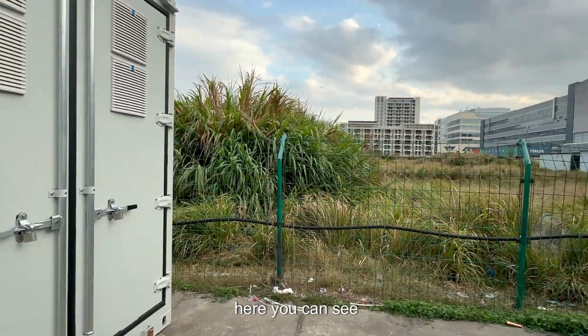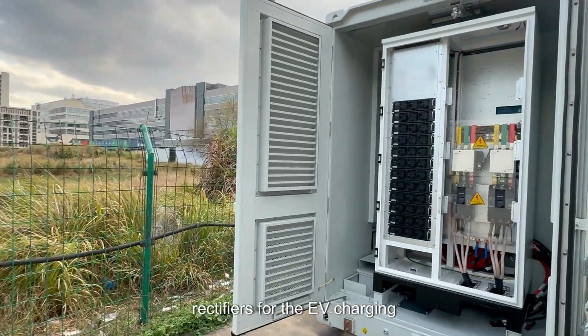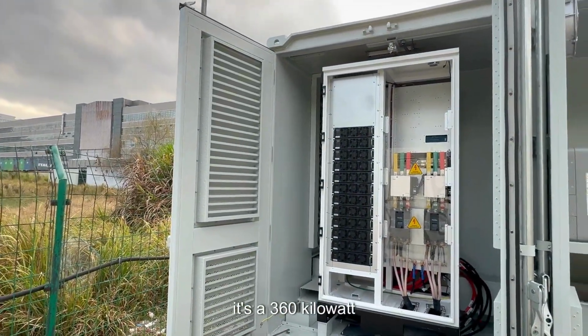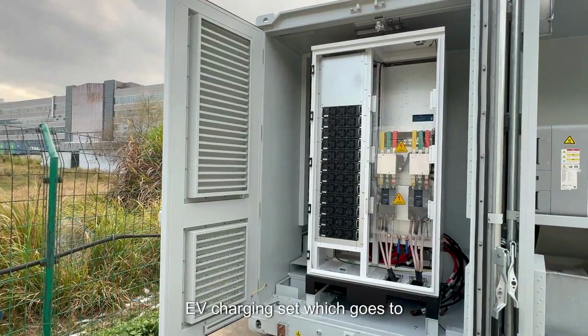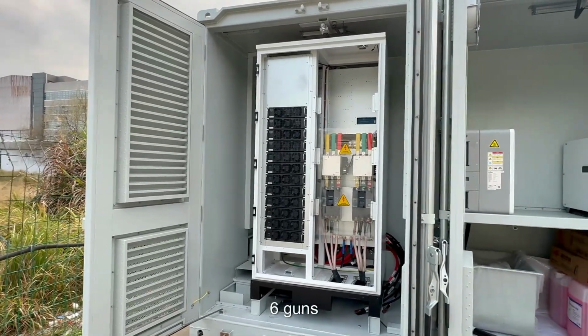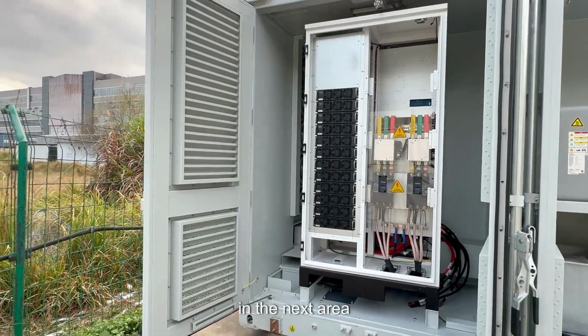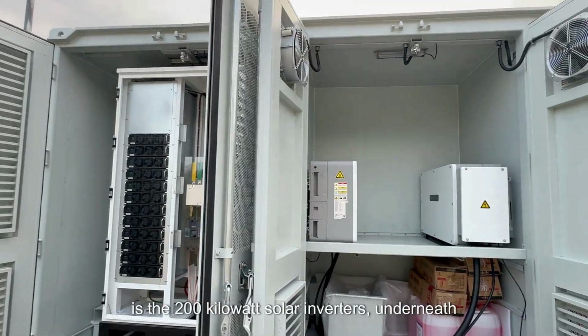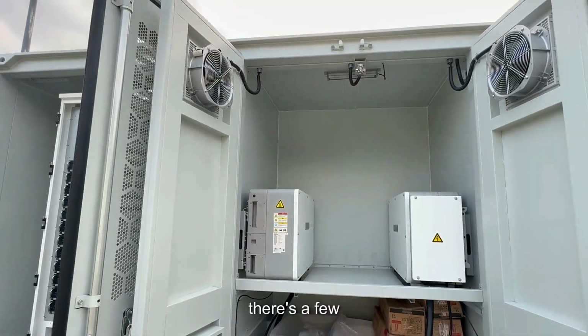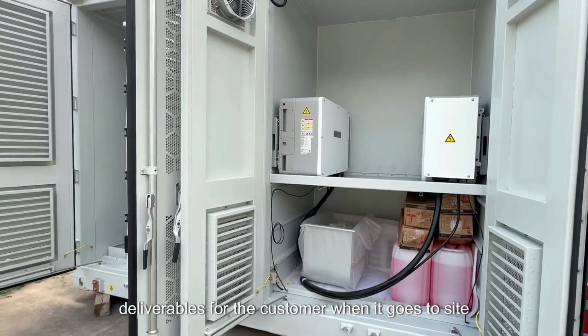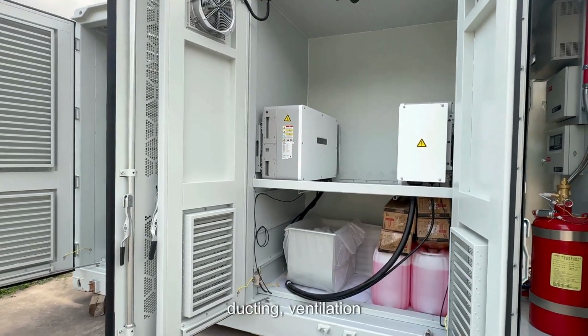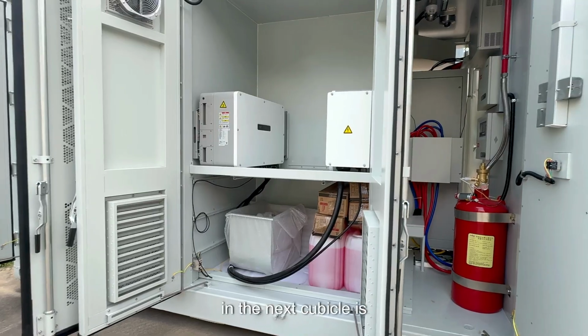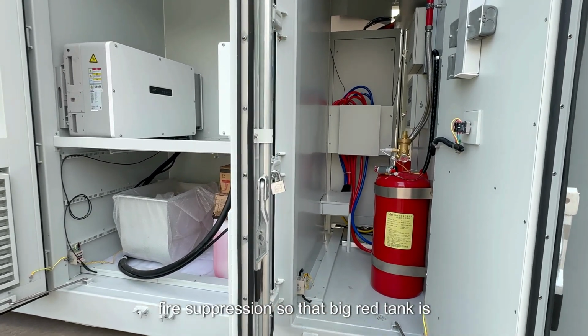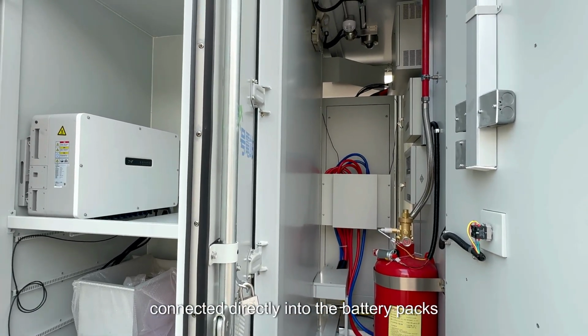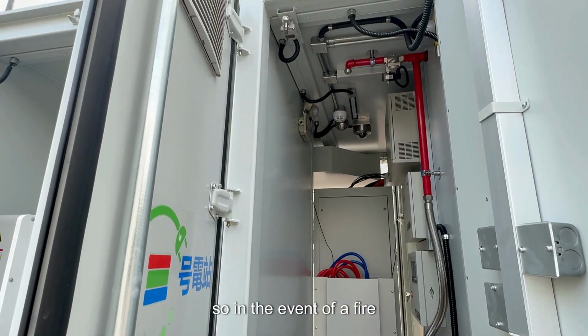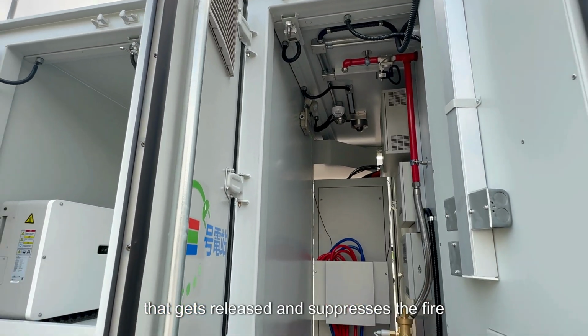At the end here, you can see the DC rectifiers for the EV charging. So it's a 360 kilowatt EV charging set, which goes to 6 guns. In the next area is the 200 kilowatt solar inverters. Underneath there's a few deliverables for the customer when it goes to site: coolant for the chiller, ducting, ventilation. In the next cubicle is fire suppression. That big red tank is connected directly into the battery packs, so in the event of a fire, that gets released and suppresses the fire.